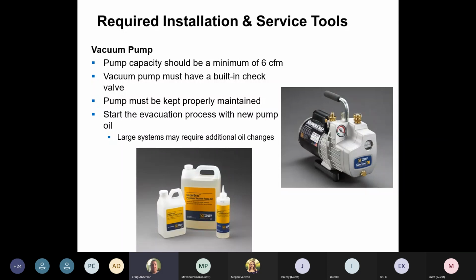Vacuum pumps. Make sure you have a minimum capacity of a 6 CFM vacuum pump. Make sure you're not using a vacuum pump that's too big. A vacuum pump that's too big, like 12 CFMs or bigger, what you're doing is you're pulling a vacuum too quick. If you're pulling the vacuum too quick, what happens inside the unit, that moisture that you're trying to get out, you're pulling it out so quick that it actually freezes. And when it freezes, you pull your vacuum, you release your freon, that freezing now melts. Now we have moisture in the system. So this is why we're going to go through a vacuum process to make sure that you're doing it properly.